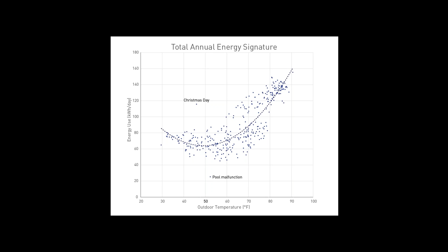By plotting both axes, we can see the base load, basically how much energy is used on a typical day not counting the HVAC system, about 64 kilowatt hours a day. We can also plot down from the lowest point of the curve to see the balance point of the project, which is about 50 degrees here. To me that says it's a fairly good envelope.